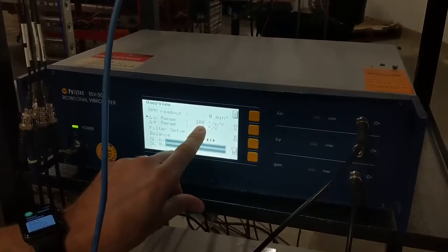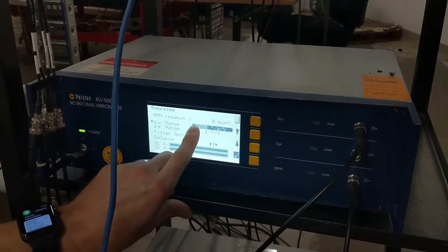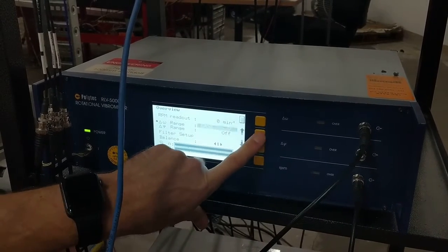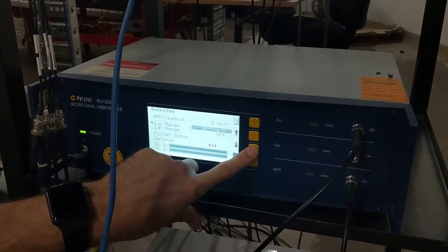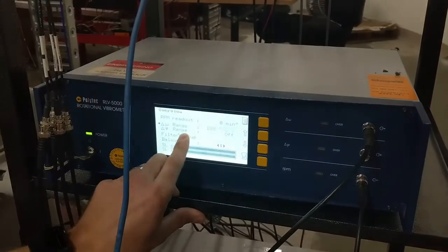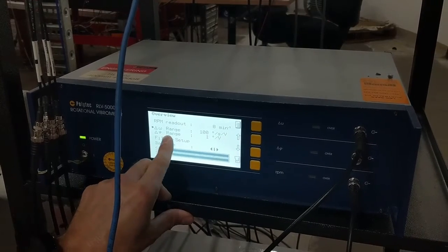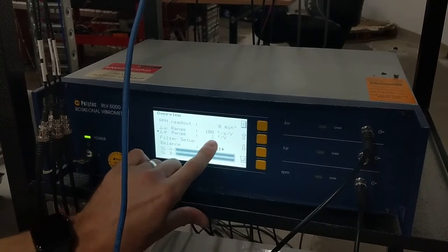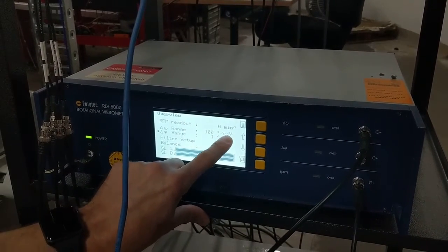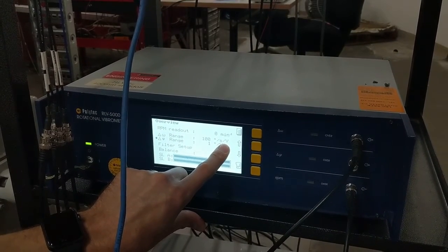We can define the sensitivity of the angular velocity signal and change that using this. If we had lots of angular velocity, we would deliberately choose a higher sensitivity. If we have less angular velocity, we can reduce the sensitivity of the instrumentation. You can see that we've turned off the delta omega there if we go for the higher rate. When we use 100 degrees per second per volt, our sensitivity for displacement output, if we were using it, would be 1 degree per volt.